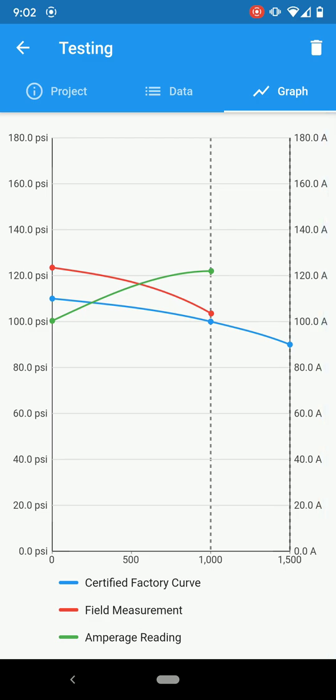I'm just picking numbers, so it's not necessarily super accurate, but you can see that the red line is the numbers we're taking from our measurements, and the dashed vertical line is our 100% point. You see we're pretty close. I had some bogus numbers there at the churn pressure, and whether there's human error or what.